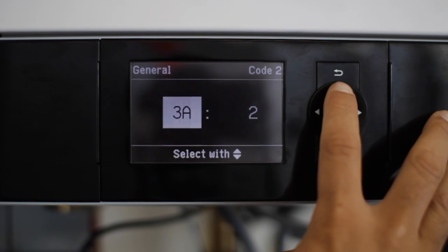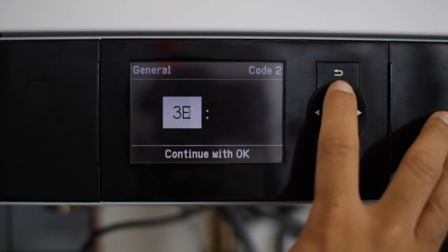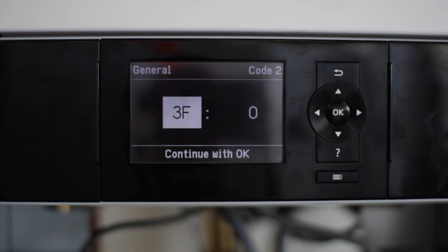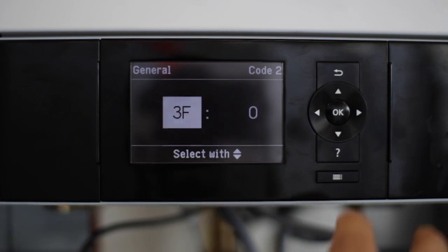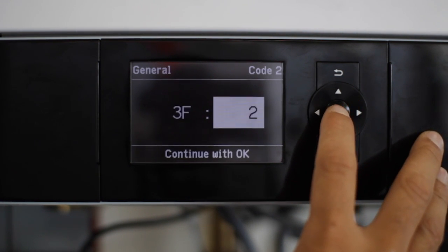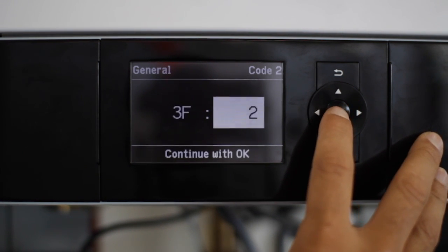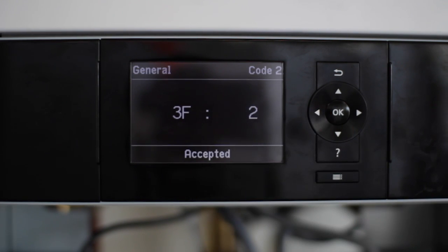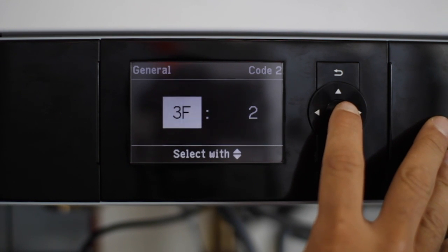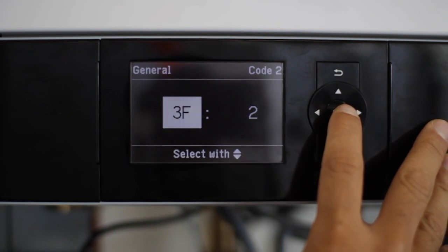The next address we're going to change is 3F, 3 Foxtrot. We're going to change this to a value of 2 as well. The value of 2 activates the boiler pump when an external demand is received. We're going to acknowledge that with OK again.